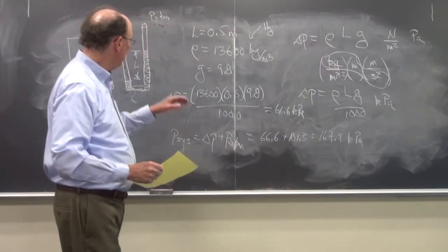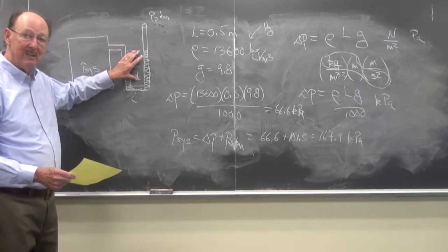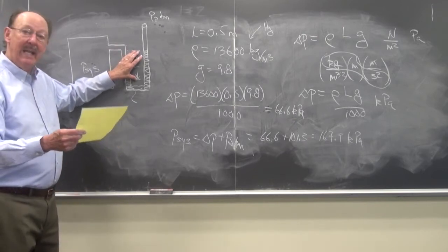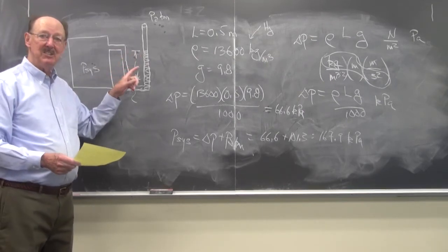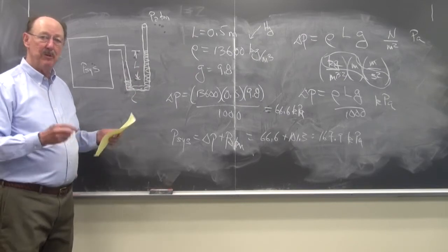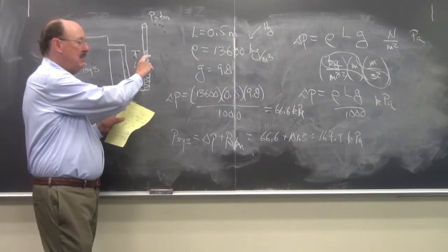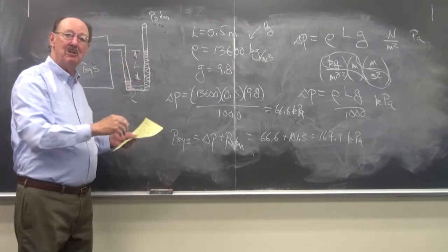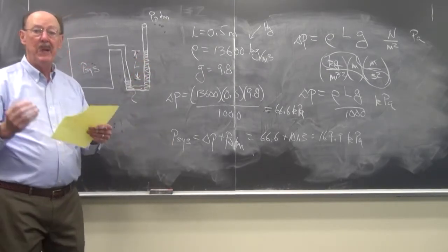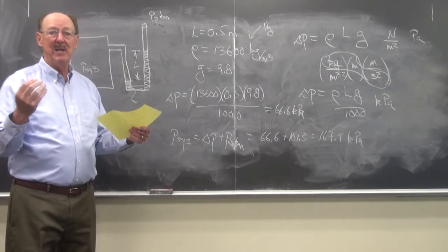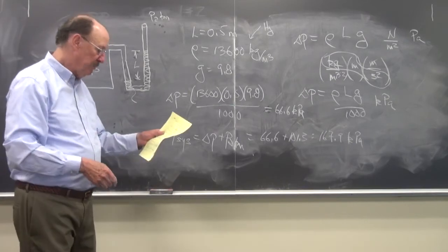So I can use the manometer to measure pressure, and I basically am going to look at L in being able to do that. And for positive pressures, sometimes we do it for furnaces and things like that, so there's a positive air pressure in there, and you'd be measuring the delta P based on inches of water. So when you're using fans and things like that, you might be measuring in inches of water, and it'd be a positive pressure. When we're measuring vacuum, we're going to be measuring it in millimeters, typically millimeters of mercury vacuum, and we'll be looking at that.